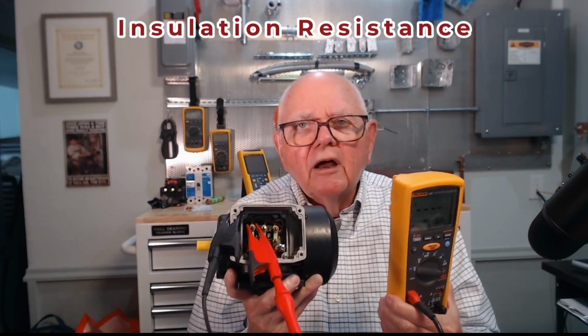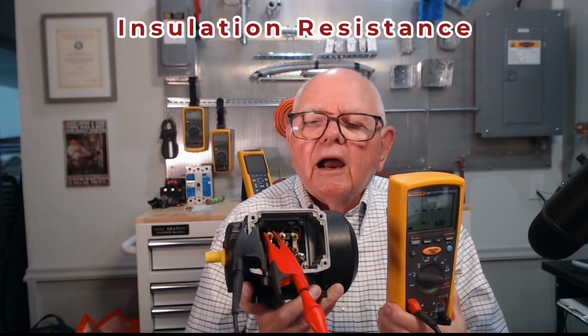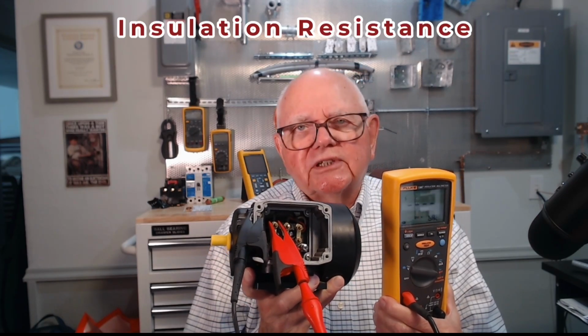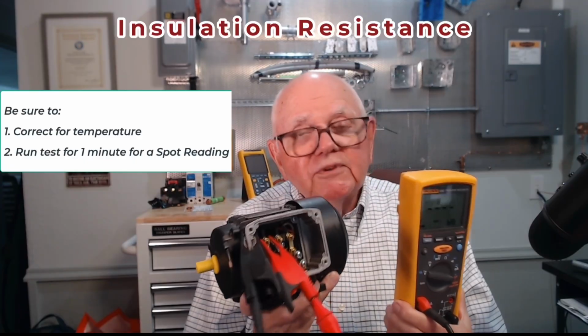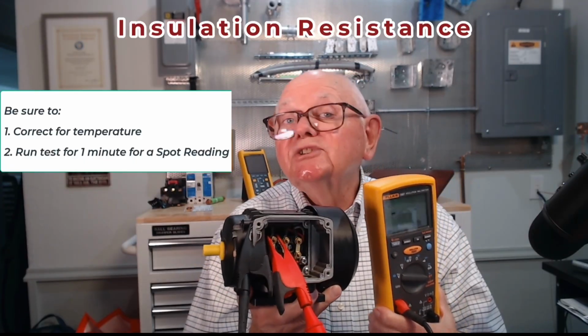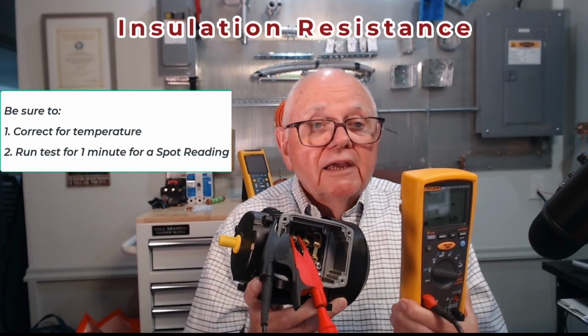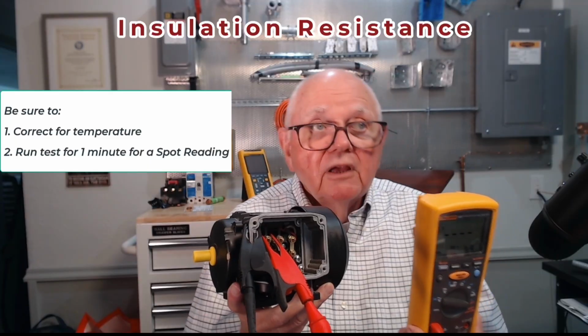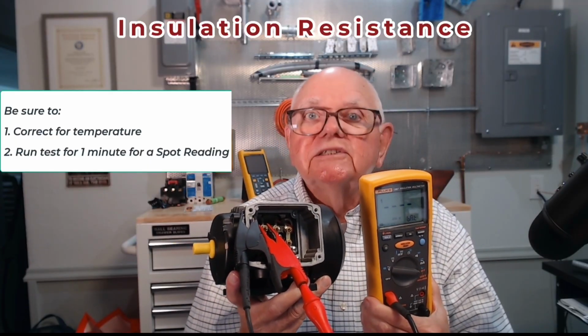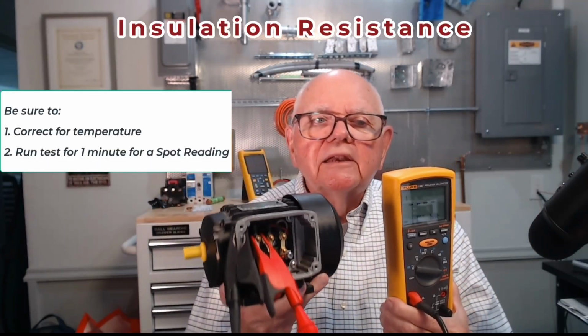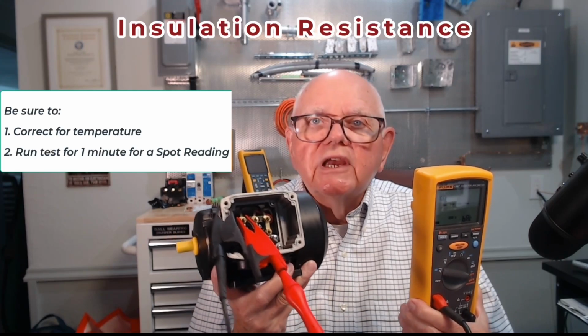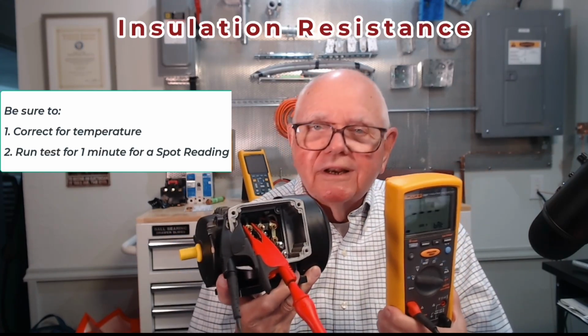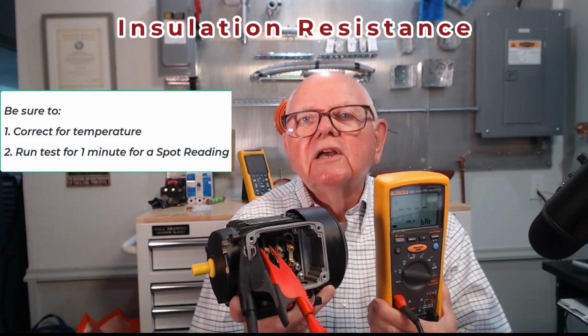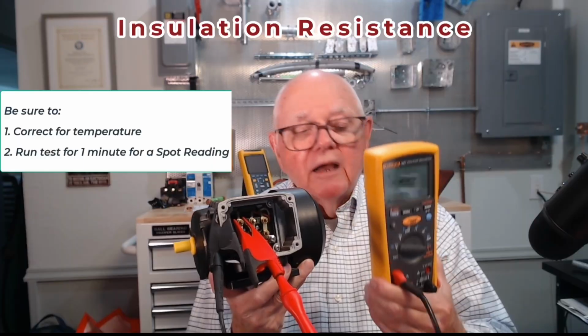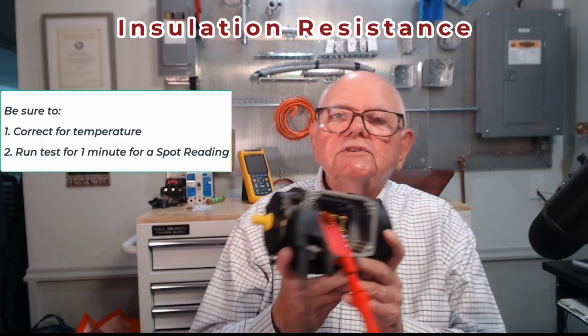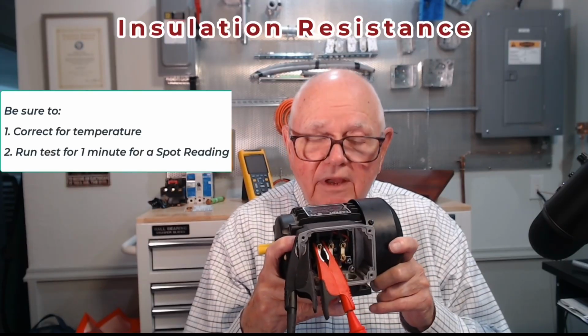Now, many of you have performed these insulation resistance tests before. The two things that I see with insulation resistance testing: number one is temperature corrections. The temperature of copper or metals will change the resistance values of that particular metal. So as the temperature of the copper changes, the resistance value is going to change. So today, if I take my resistance reading at 18 degrees C, and next month I come along to do my maintenance and I take my reading at 38 degrees C, how has that affected the resistance? Well, I don't really know. So I'm going to correct my resistance values to a particular temperature. All right, so I'm going to use the tables that come with my insulation resistance tester and other resources that I can find, and make sure that I make my temperature corrections.